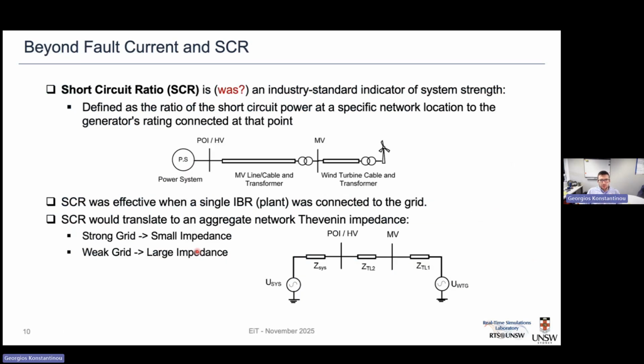Now, some examples of short circuit ratio. The traditional definitions, even with power electronics converters, looked at the ratio of the short circuit power following fault calculations at a specific location relative to the rated capacity of the generator connected at this particular point. This was a relatively straightforward definition because even with a single plant connected to the grid, we could very easily look at the aggregate Thevenin equivalent.